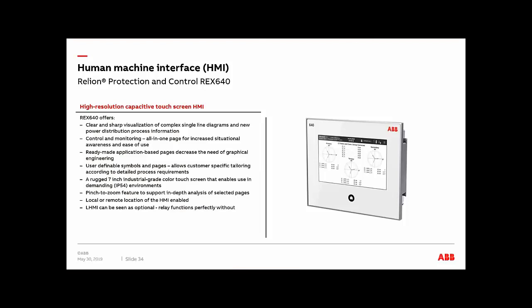Moving on to the HMI, human machine interface. On this one, we're going to have a very nice 7-inch touch screen HMI on the relay. So you're able to do control and monitoring from the HMI. We're going to give you ready-made applications based on pages that are preloaded on the base configuration of the relays. Depending on the package that you have ordered, you will get the respective HMI typical configuration. The screen itself is detached from the relay, connected through an RJ45 type of cable. It's IP54 for rating. So we're gonna talk a little bit more in detail about the HMI here.